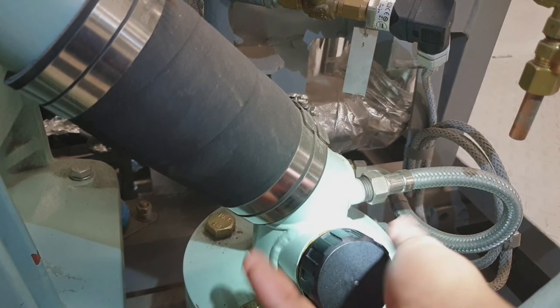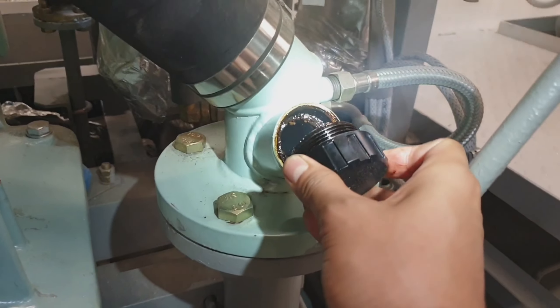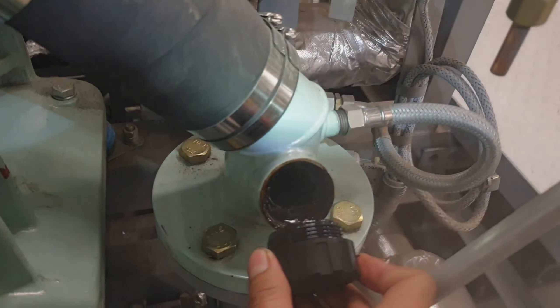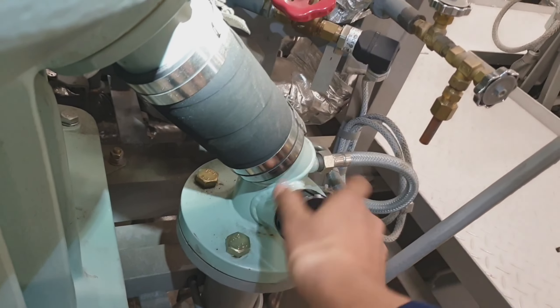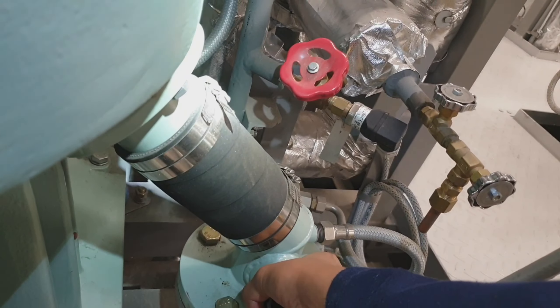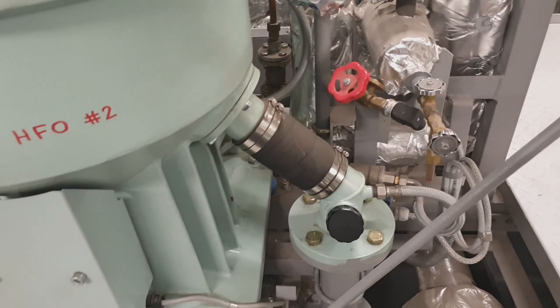As you can see, you can observe any abnormalities and any leaking here visually. You have to check this and keep in mind that the purifier can dislodge, so just bear in mind to check if it is dislodging or not before opening this inspection hole cap.